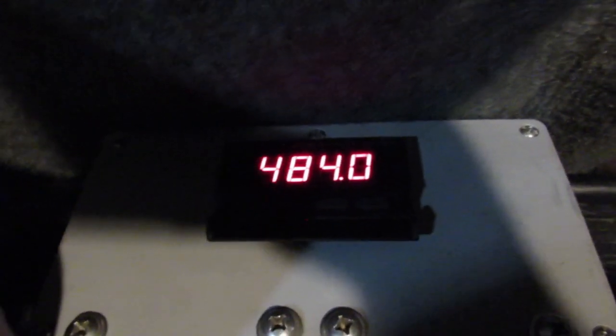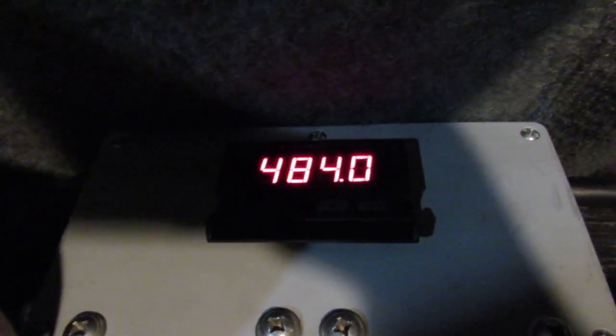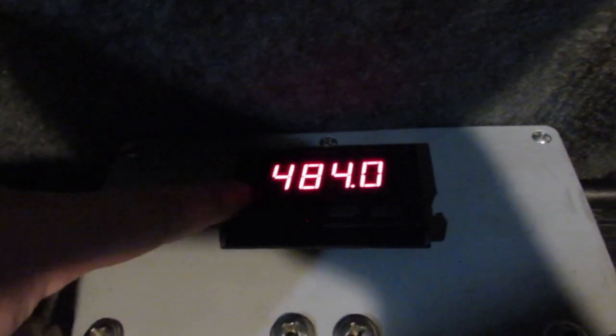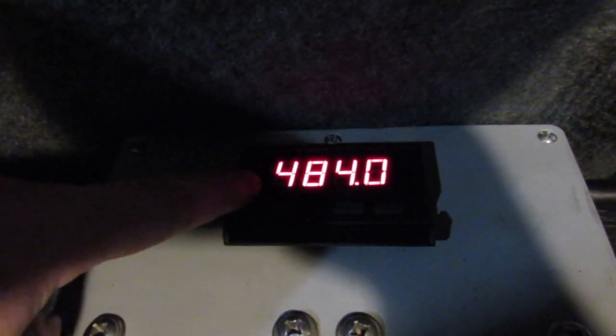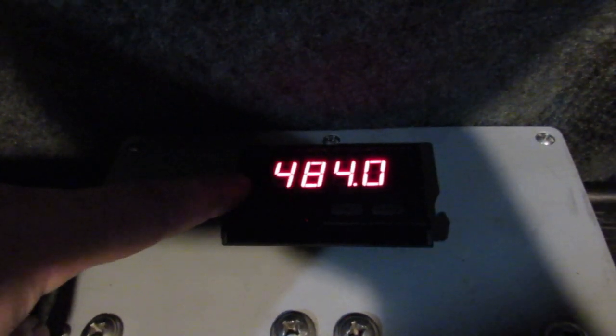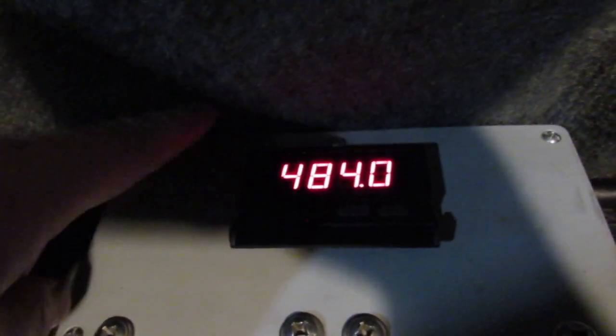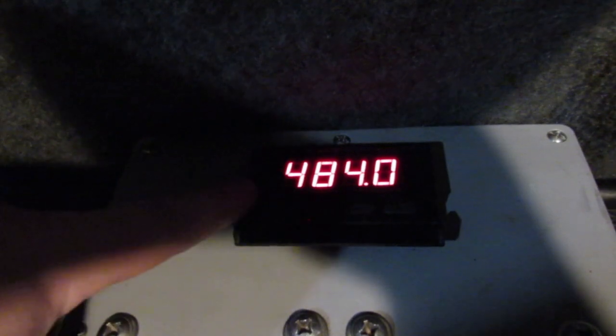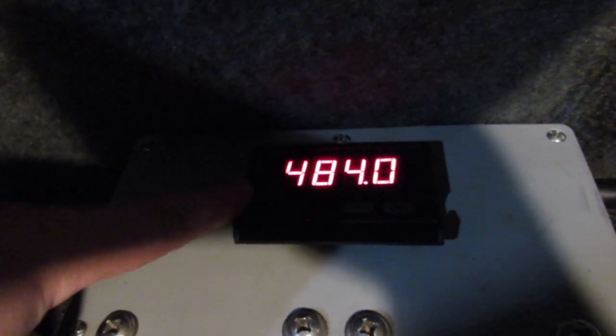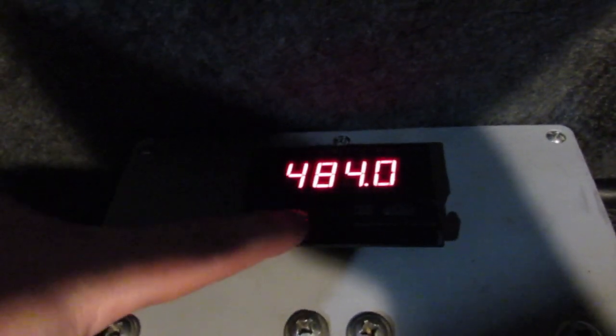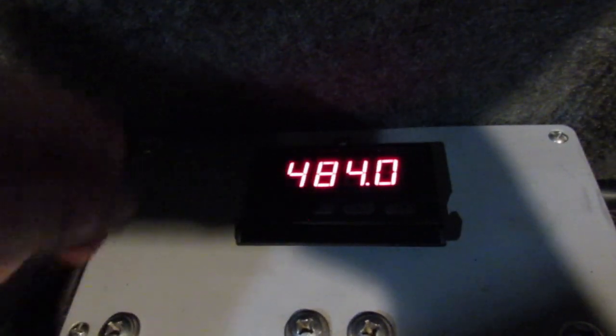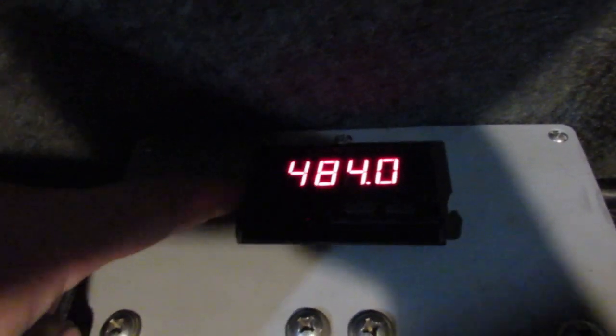With this particular meter, I have it set to 484. So this is like what max a 500 volt reading would read. If it saw 484 on the meter, that would really mean 500 volts if it actually had a 500 volt input.